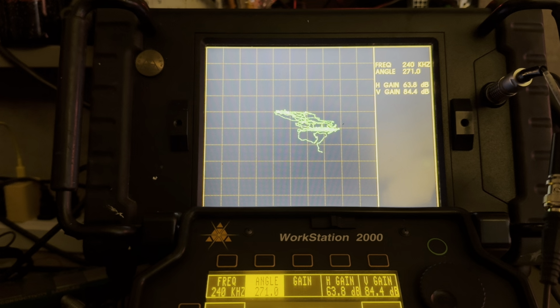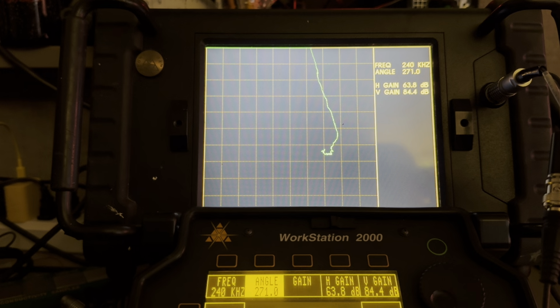Now that impedance point's moving around a bit, right? But you're not getting a lot of vertical deflection. You're just getting a lot of horizontal motion, right? And you're probably thinking, well, what if there's a flaw in there? I'm just not really recognizing it. Well, a good test now is to go over to your cal block that you know has a crack in it, which would be this guy.